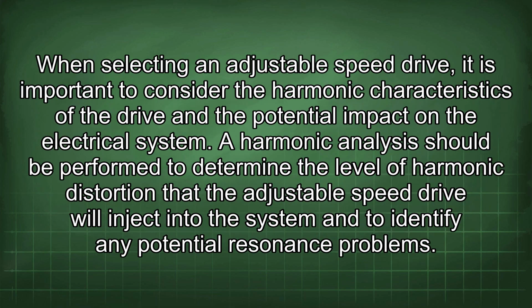When selecting an adjustable speed drive, it is important to consider the harmonic characteristics of the drive and the potential impact on the electrical system. A harmonic analysis should be performed to determine the level of harmonic distortion that the adjustable speed drive will inject into the system and to identify any potential resonance problems.